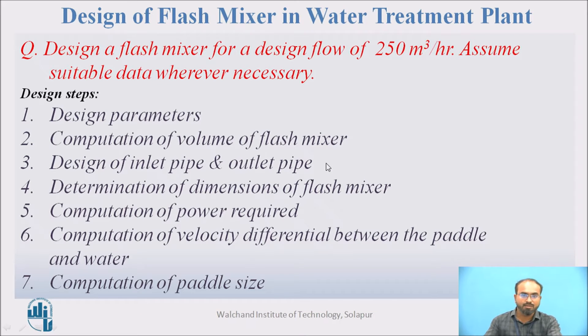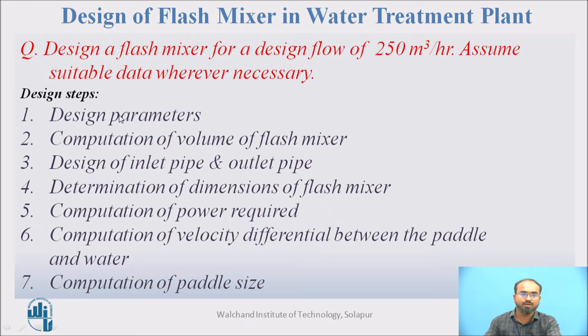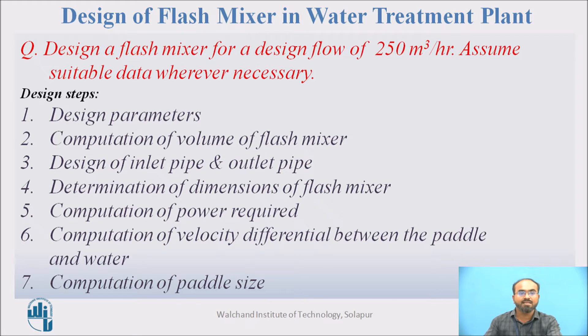Let us take a numerical example to design a flash mixer for a design flow of 250 meter cube per hour. Assume suitable data wherever necessary. The typical design steps are: first, design parameters; second, computation of volume of flash mixer; third, design of inlet and outlet pipe; fourth, determination of dimensions of flash mixer; fifth, computation of power required by the paddles; sixth, computation of velocity differential between paddle and water; and seventh, computation of final paddle size.